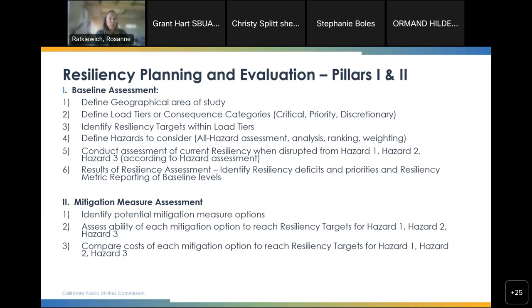So what do we want to protect and where is it, is covered by defining our area of study, understanding our load tiers or priority categories, consequence categories, and our resiliency targets within those load tiers. Do we want to identify that our minimum target is 100% of all critical identified loads, and then maybe another 50% of identified priority loads, and then whatever else we can potentially fill in with discretionary resources?